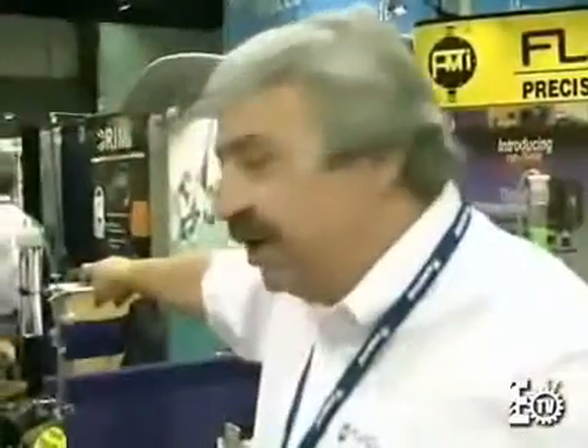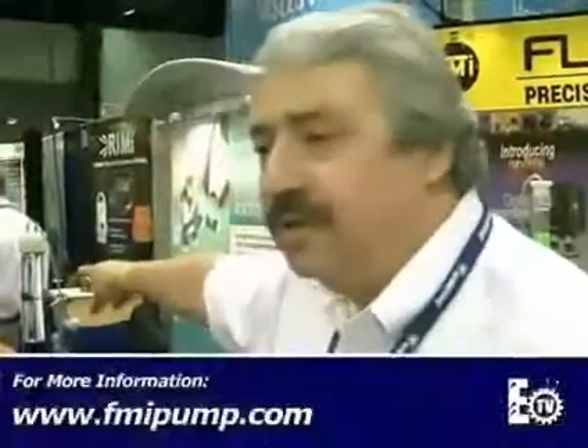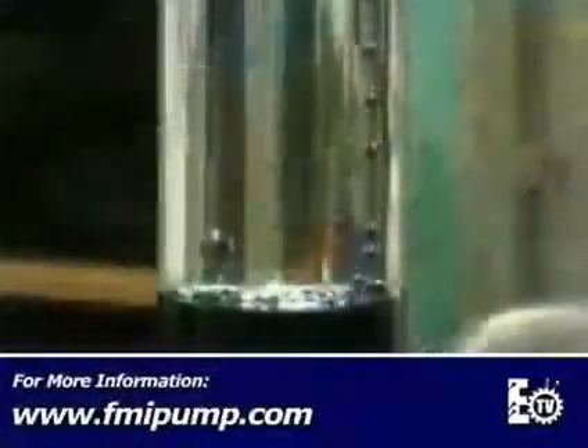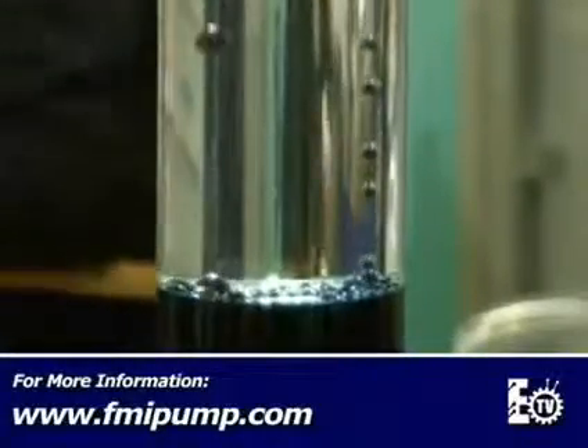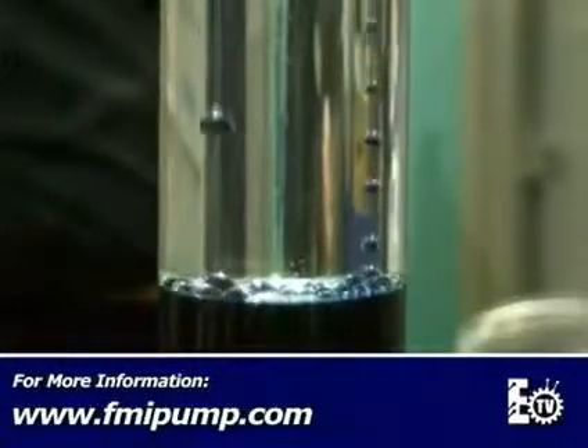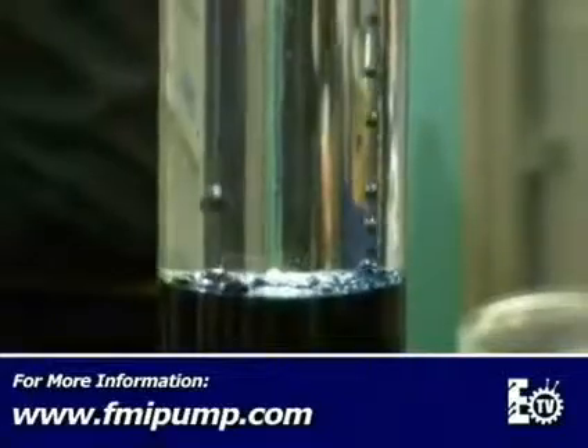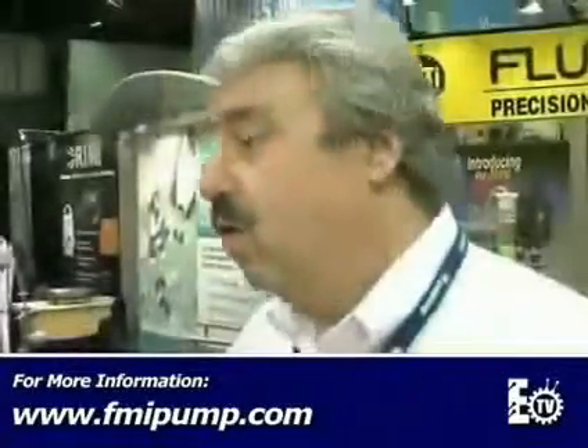The one on the very end over there, you'll see two different size droplets. Again, that's off of one unit that has two pumps in there, independently controlled. So we could do lots of different ratiometrics, ratio feeds and so forth, or just doubling up as far as having a larger volume that we need to pump and meter. So you basically have one piston that both moves the fluid and meters it at the same time, right?